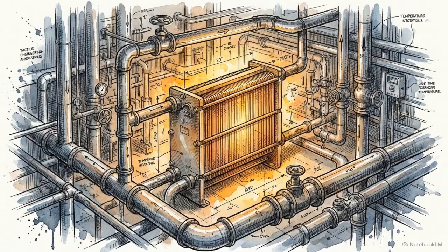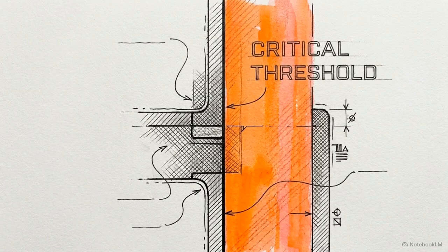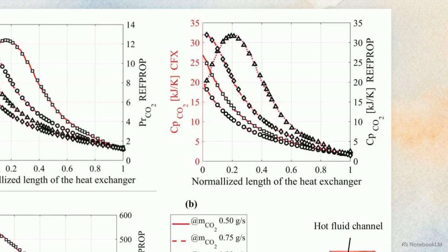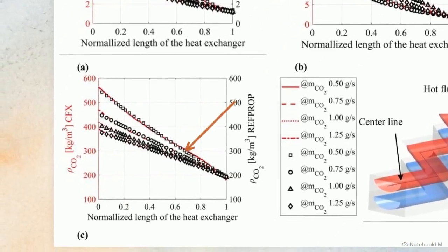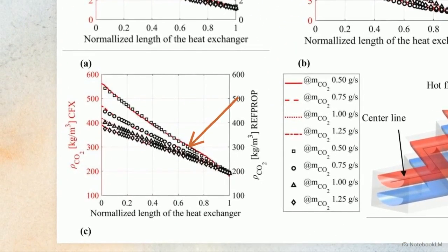The efficiency of the entire power cycle hinges on a single heat exchanger forced to operate in the most unstable fluid regime imaginable. That instability happens in the pseudo-critical region, a highly volatile, narrow temperature band sitting just above the critical point of the CO2. This chart maps the fluid's specific heat capacity. Inside this boundary, CO2's ability to absorb heat violently spikes, reaching values 40 times higher than liquid water. Simultaneously, as the temperature shifts across this exact same narrow boundary, the fluid density drops off.